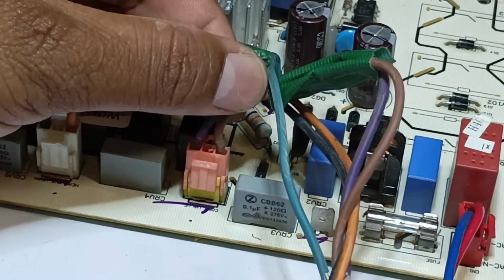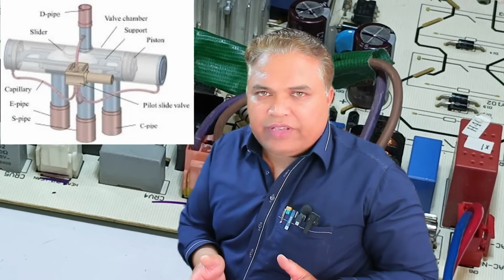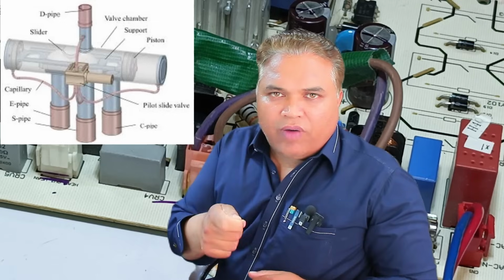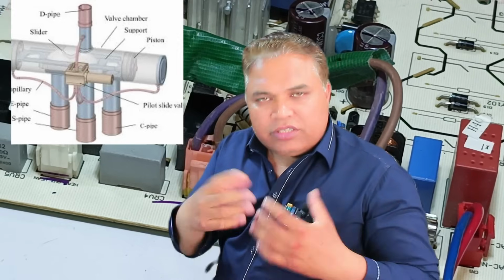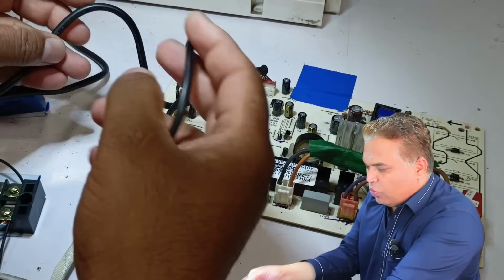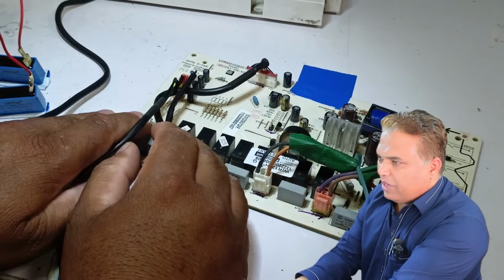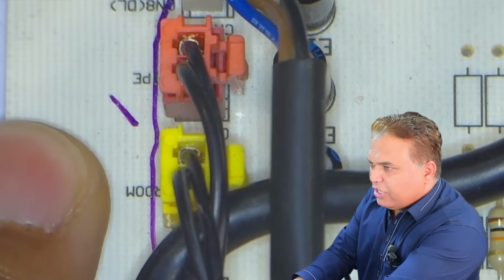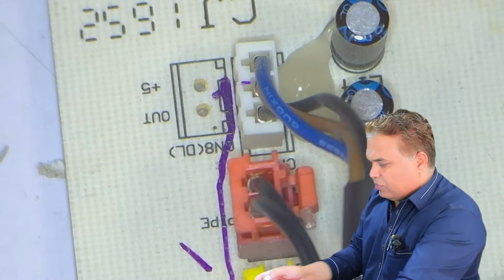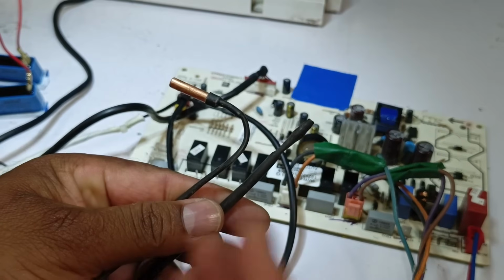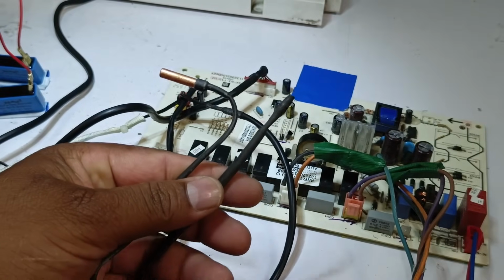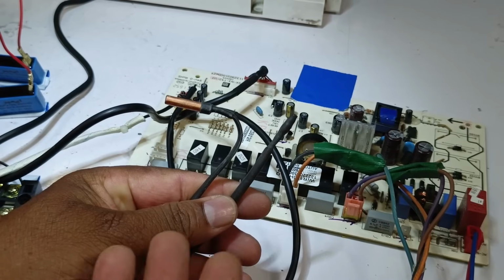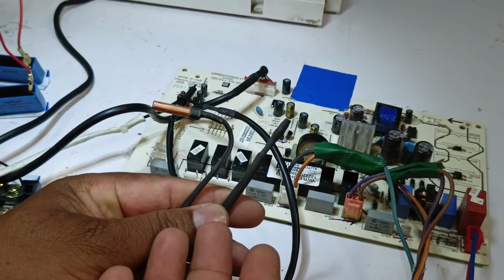Similarly, the purple wire is connected to the heat and cool reversing valve, also known as the four-way valve. This valve is activated and deactivated through this wire, allowing the system to switch between heating and cooling modes. In addition to this, the indoor unit manages several other control functions, including sensors. There are two main sensors inside the indoor unit: one for room temperature, one for the pipe coil temperature. These are standard in most air conditioners and are used by the indoor unit to control the system's operation.